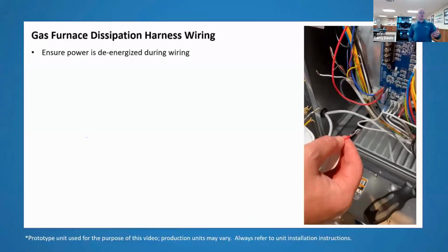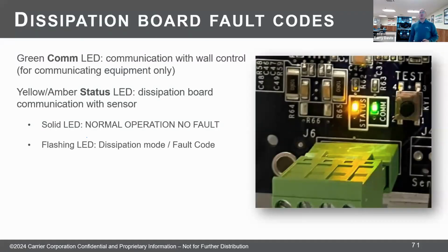All they were walking through is what we just talked about on wiring it up. So that harness will come down. You'll see the R has a piggyback on it. You pull your secondary one off and plug that on, plug your secondary one back on. You're out to the furnace and then on out to the outdoor unit. And you're in from your thermostat wire nuts to the wires in the harness. Okay, they'll all be clearly labeled.